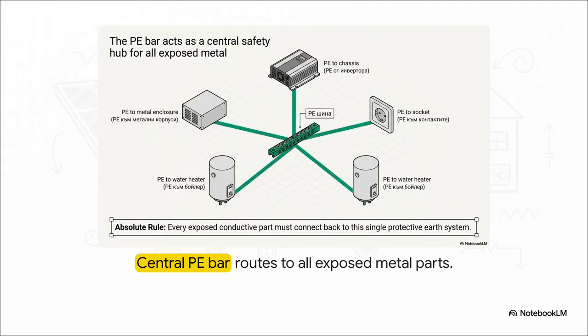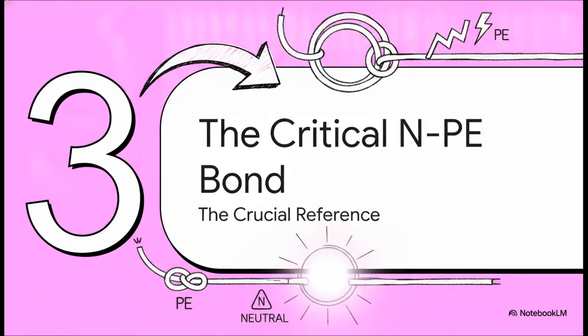Once you've got that hub established, we have to strictly follow what I call the absolute rule. Every single piece of exposed conductive material, the inverter chassis, the metal enclosures, your water heater, the whole shebang, has to route directly back to this one central PE system. If it's metal and it could potentially carry a fault, it gets wired to that PE bar. No exceptions. Which brings us to section 3, the critical NPE bond.